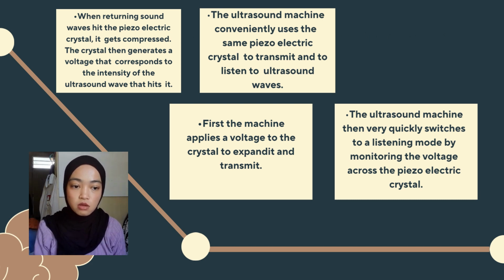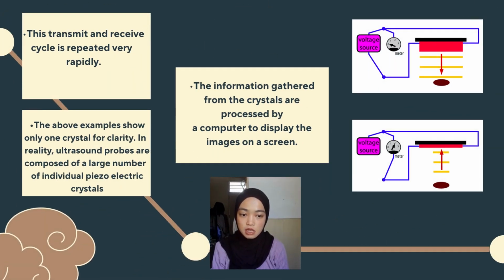The ultrasound machine conveniently uses the same piezoelectric crystal to transmit and to listen to ultrasound waves. First, the machine applies a voltage to the crystal to expand it and transmit. The ultrasound machine then very quickly switches to a listening mode by monitoring the voltage across the piezoelectric crystal. This transmit and receive cycle is repeated very rapidly. The examples show only one crystal for clarity. In reality, ultrasound probes are composed of a large number of individual piezoelectric crystals. The information gathered from the crystals is processed by a computer to display the image on the screen.